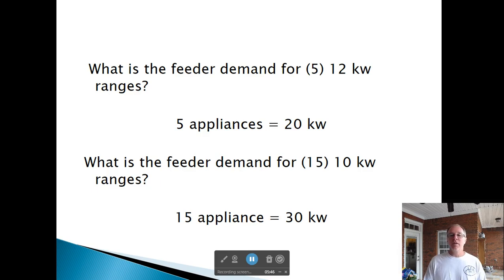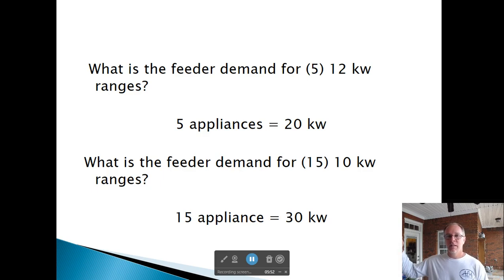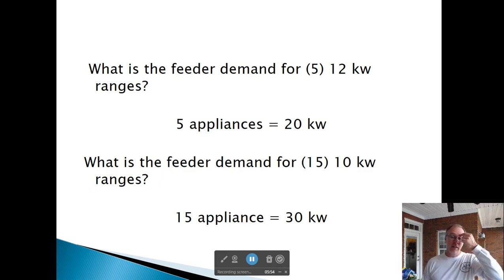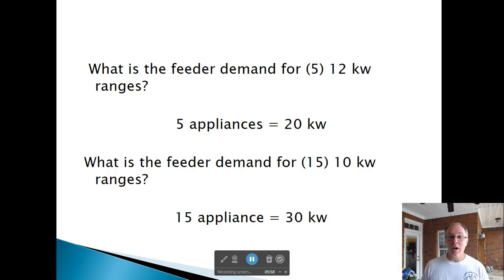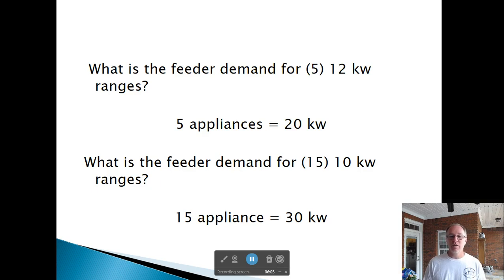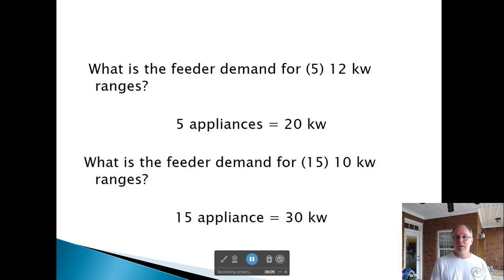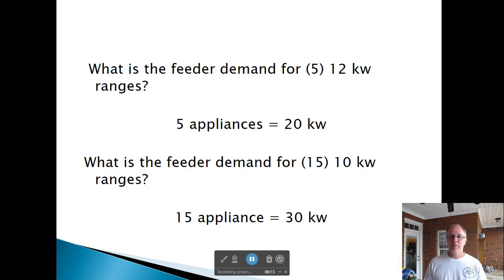What's the feeder demand for five 12 kW ranges? Five appliances — go to Column C — it's 20 kW. What's the feeder demand for 15, 10 kW ranges? 15 appliances, go over there — it's 30 kW. It's as simple as that.